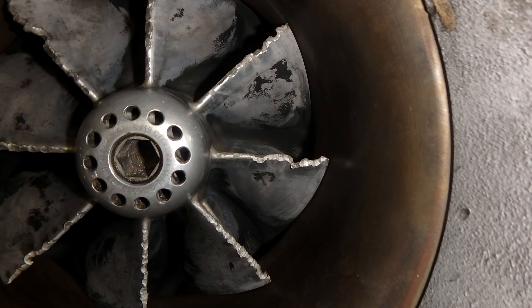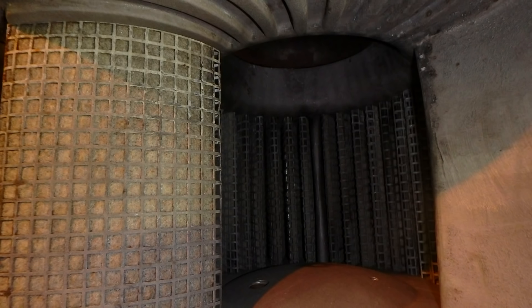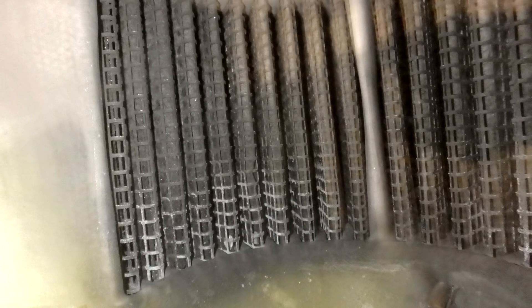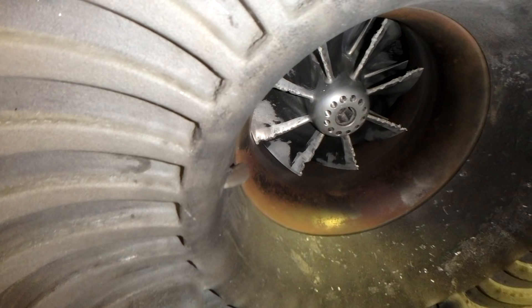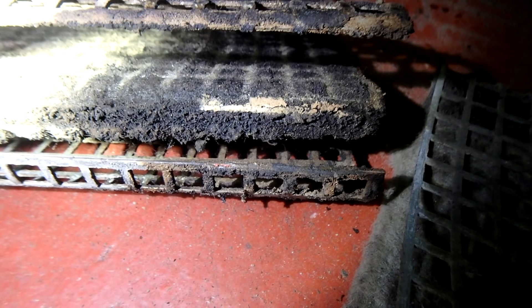You can see some blades were damaged — maybe some parts passed through somehow — but it is really difficult to imagine exactly what was going on. When I came on board, I saw one plastic duct attached on the turbocharger silencer. I asked the previous crew why it was placed there, and they told me they put the plastic duct because they had a temperature problem on the exhaust gases of the cylinders. This told me there was not enough air passing to the diesel generator through the silencer.